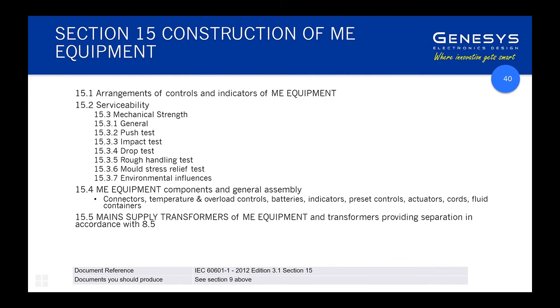Section 15 covers construction with a specific range of tests that apply to the mechanical aspects of the equipment. There's a lot of interaction between the mechanical and electrical — some of these tests aim to ensure that abuse of the equipment cannot cause the enclosure to crack or a gap to open up that then leads to an electrical safety hazard. You need to make a judgment about how much of this testing you do in-house versus farming out to test labs.